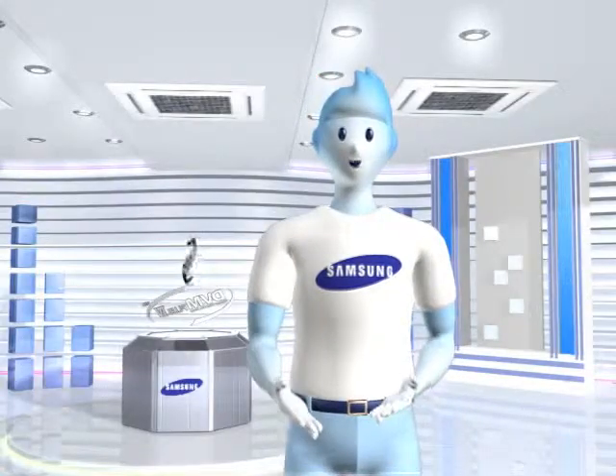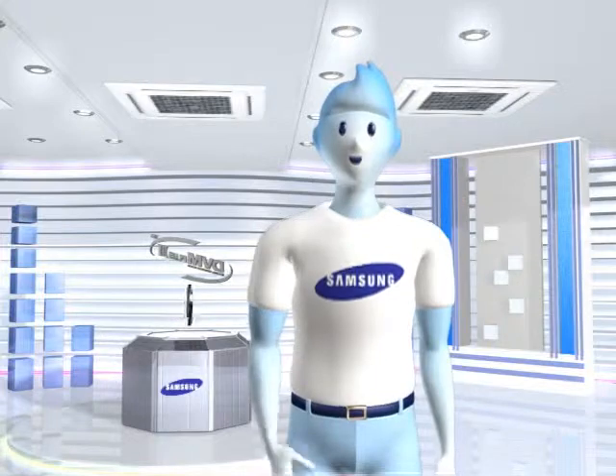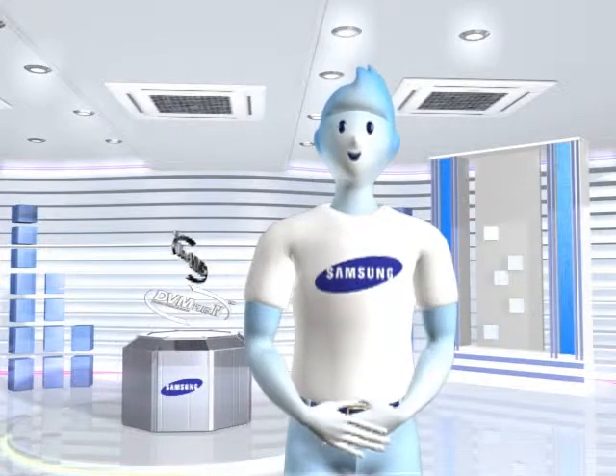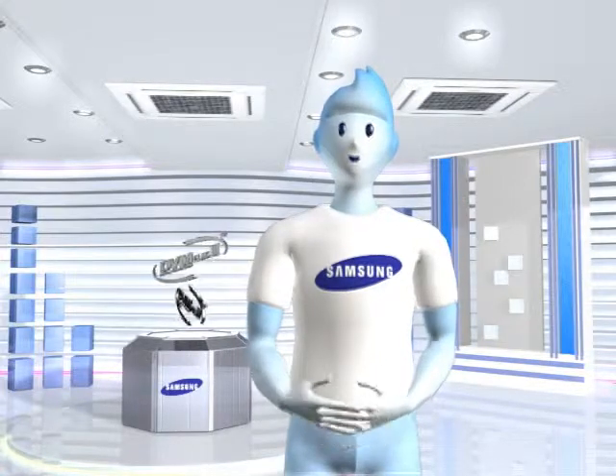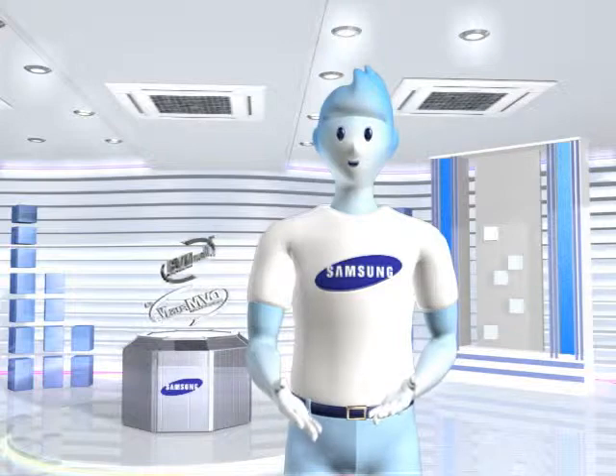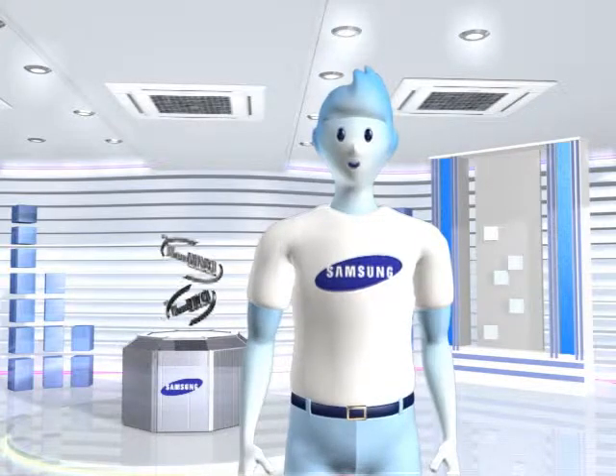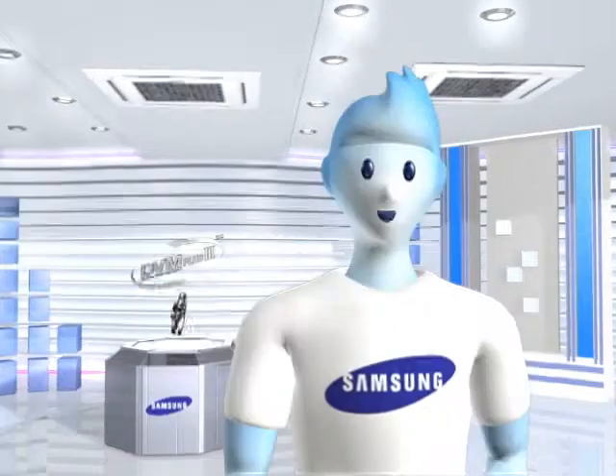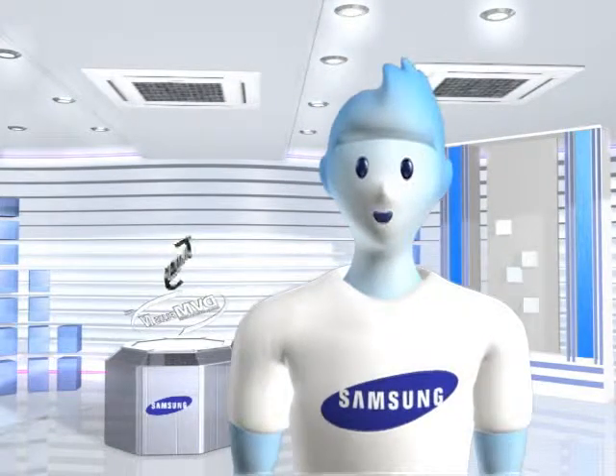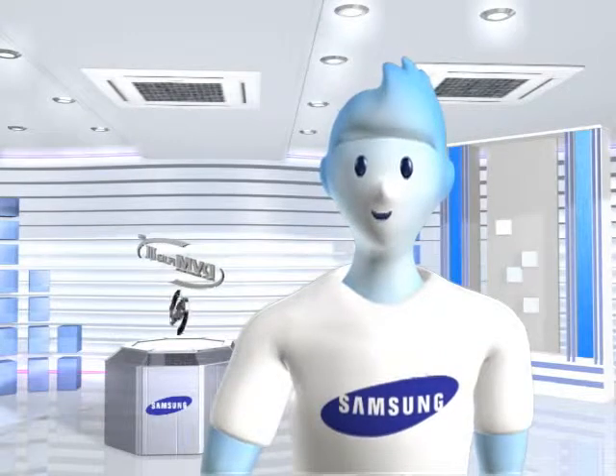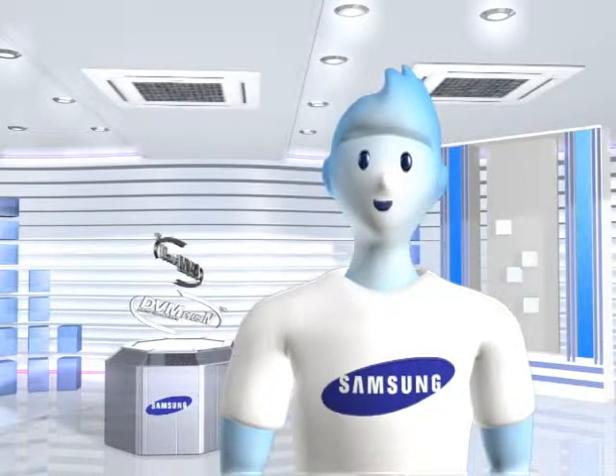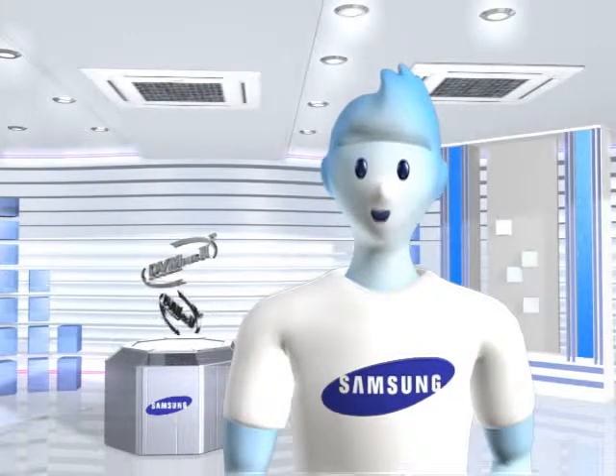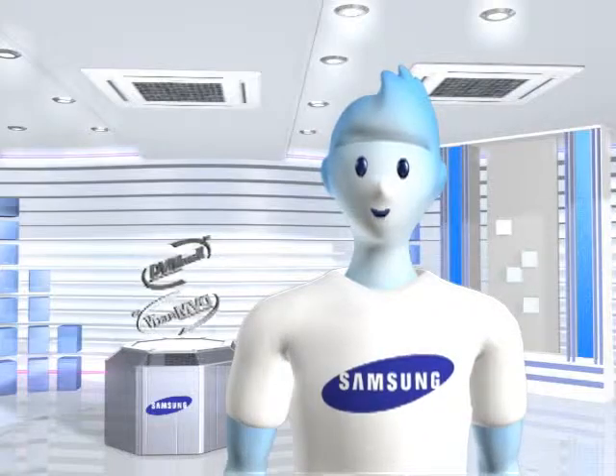An air ventilation system is likely to cause dew forming in the heat exchanger when the humidity and the temperature are too high. You should not use it in a place with relative humidity of more than 80% and temperature of higher than 30 degrees, such as swimming pools, bathrooms, mushroom farms, or a place with lots of fog or dew. In addition, you should be careful with the connection between ERV, the air inlet, and the air outlet, and the duct. Why is that?